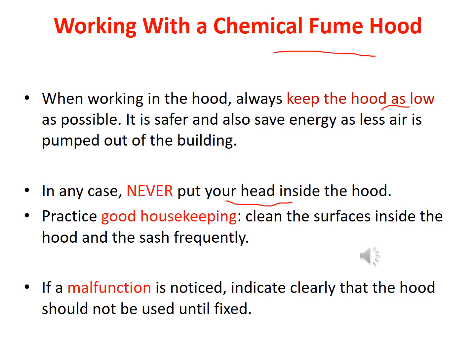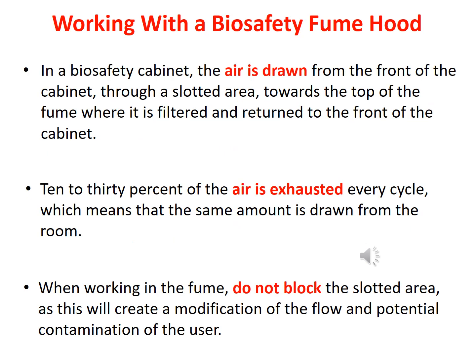And of course, if you find any malfunctioning of the hood, then don't work on that hood, and just report the incident to the technician or the supervisor. While working on biosafety fume hoods, it is really important to understand the nature of the cabinets. For example, in a biosafety cabinet, air is drawn from the front of the cabinet through the slotted area, and then goes to the top, where the air is filtered and returned back to the front of the cabinet.